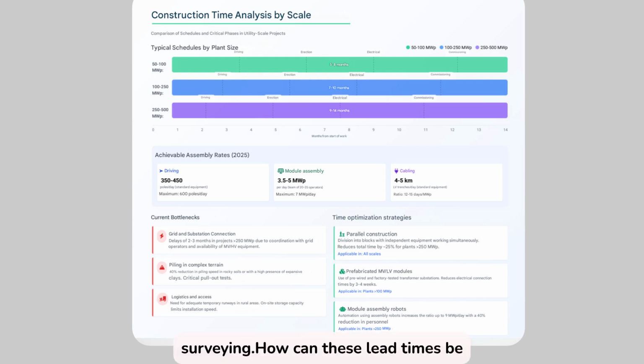How can these lead times be reduced? Let's look at three key points. Parallel construction: dividing the plant into independent blocks with simultaneous equipment. Savings of up to 25% on large projects, over 250 MWP. Prefabricated MV/LV modules: use pre-wired and factory-tested transformer substations. This saves 3-4 weeks on electrical connection. Module assembly robots allow for rates of up to 9 MWP per day with 40% less personnel. Highly recommended for plants over 250 MWP. These strategies are already being applied in projects in Brazil, Chile, and southern Spain, with good results.